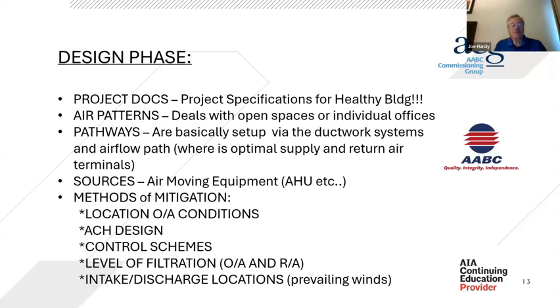Intake and discharge locations are important, of course, for labs. I had a job a few years ago, actually two jobs, both at schools. One had a problem where the plumbing vent, even though located the correct code distance from the outside air intake on a rooftop unit, had its odor pushed by the prevailing wind so it could actually be smelled inside from that unit. Then there was another one, a high school.